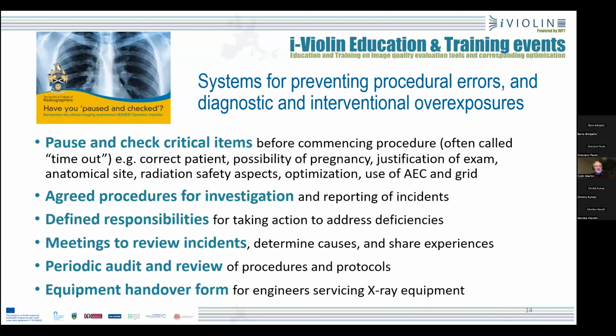And something which is quite useful is to ensure that when the X-ray engineers from the maintenance department take over a room to carry out maintenance, everybody is aware that they then have the responsibility for radiation safety, and that's been formally handed over to them.